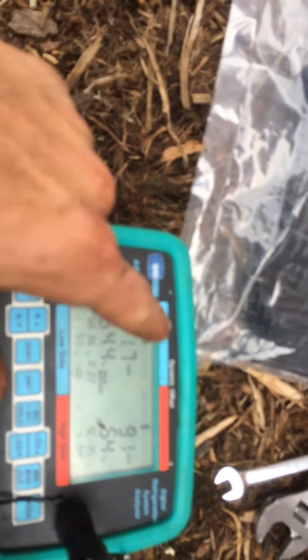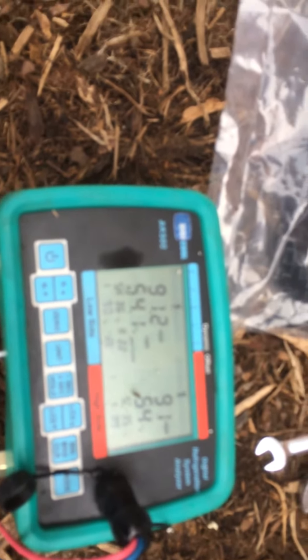You can leave it on for 10 minutes or so and watch the top. Each one of those little bars is like a quarter PSI — you can't even get close to that resolution with analog gauges. I don't know what guys are talking about who think analogs are great, because they're not. I thought they were until I went digital, and digital wins all around — there's just no comparison.